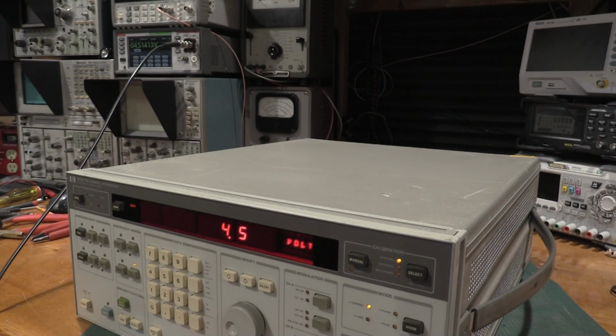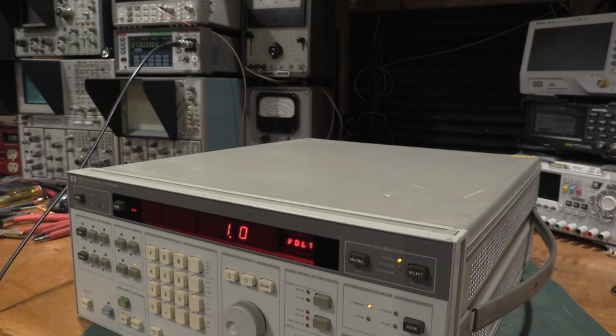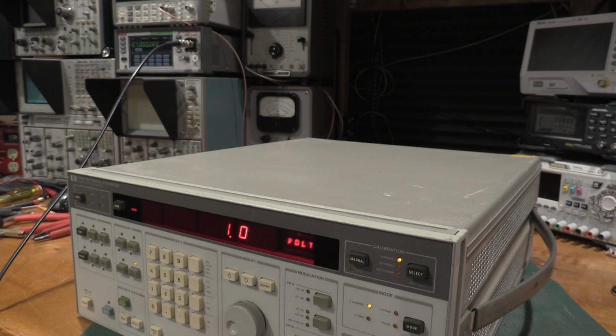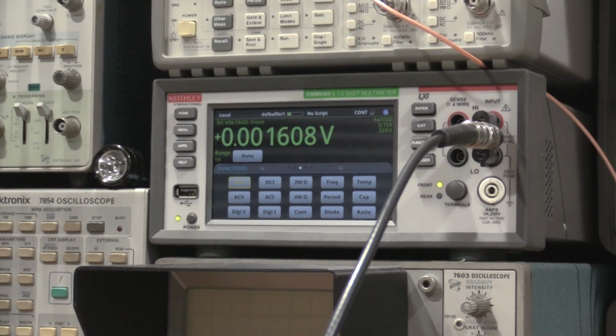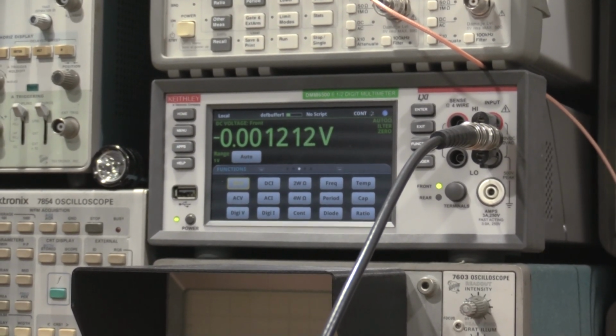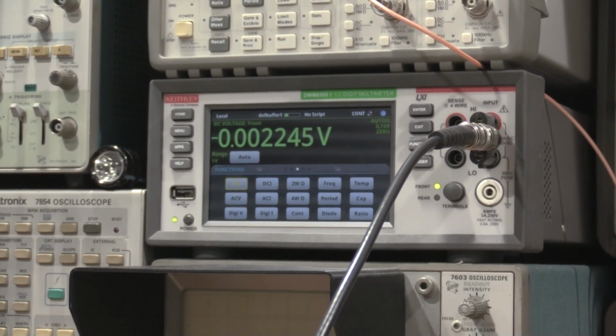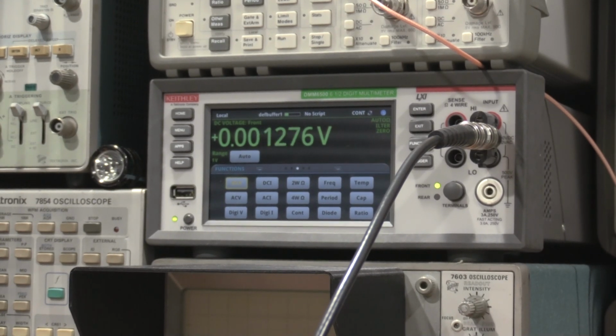Yeah, it was channel A that was doing it. So I am guessing we either need to do a full alignment, check the reference, do a couple other things, or we need to put some relays in this particular unit. But we have made vast improvements because it actually has a brain, and it's 98% there. One other thing to add is it will do a 0 volt offset without a problem. It just won't calibrate a 0 volt offset. So this is what leads me to believe it is some of the small signal relays in this particular unit.